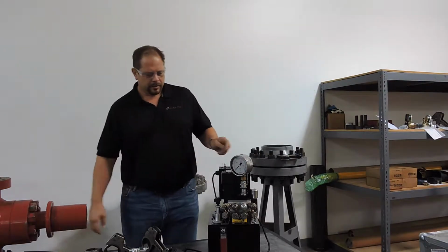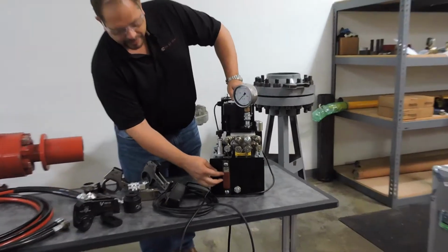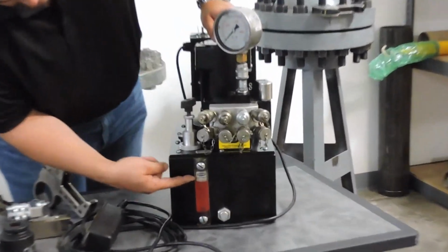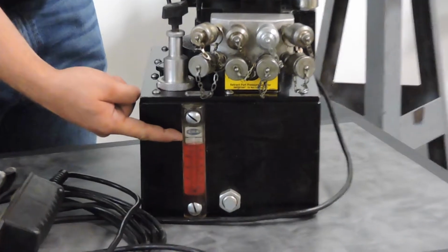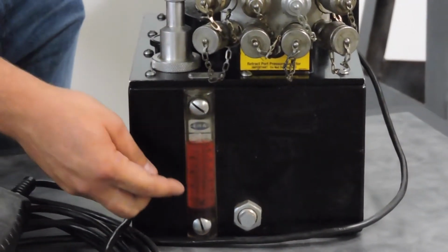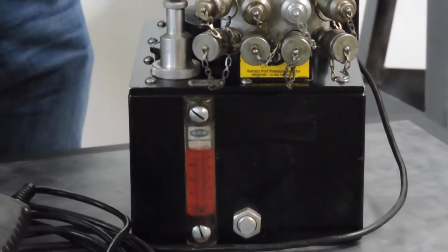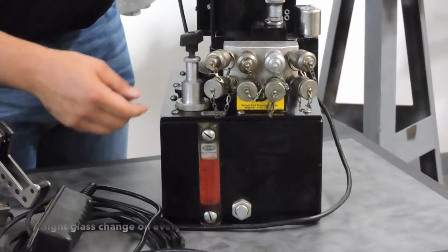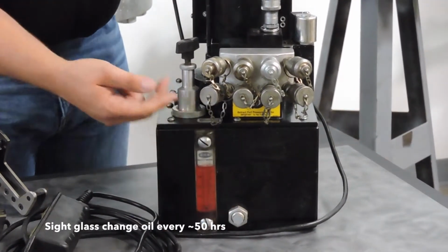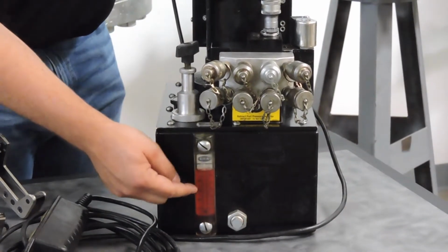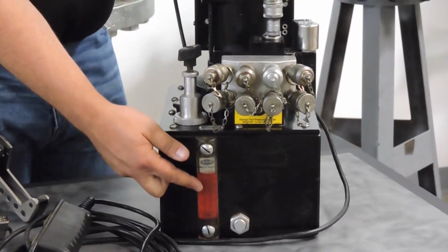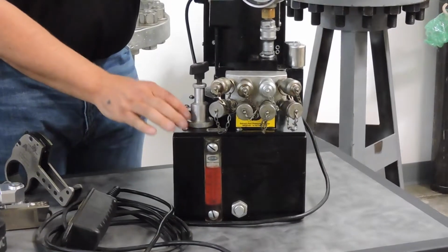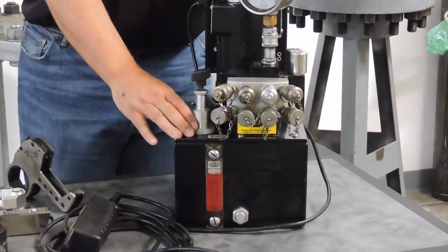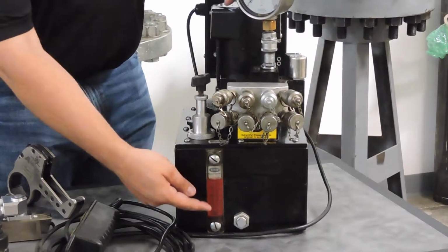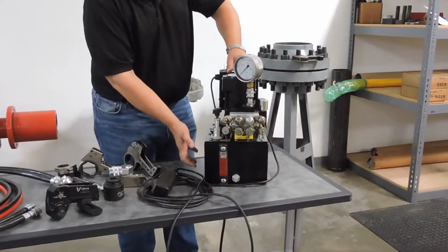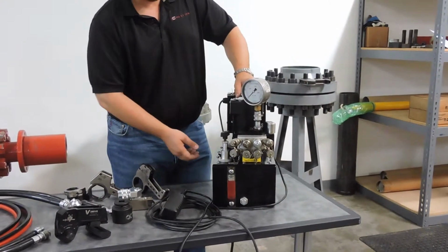You'll see the oil capacity in the sight glass here. There is a line that goes right across the top. That will tell you that your oil is full. If your oil is milky, if it's white, or it needs to be changed out, there's a drain plug in the front. You can drain the oil out. It takes 2 gallons of oil. This is red. It's our specific oil. It is not transmission fluid. If you have to add oil to one of these pumps, you need a grade 46 non-foaming oil. You want to, before a job, make sure that you have enough oil in here so that the heat can dissipate in the oil and your pump won't overheat.